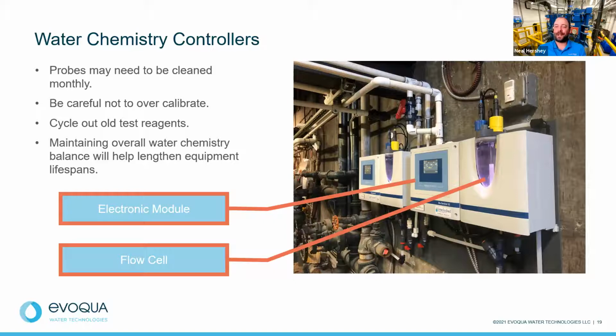You've got the electronic side that shouldn't really require any maintenance, but it's that flow cell side, the wet side, that's going to require routine maintenance: cleaning the probes, periodic calibration, and just a visual inspection to see what's going on with your water. That's usually a key visual indicator.